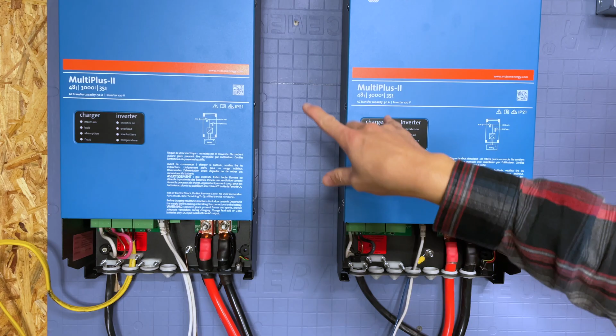So what that really means is it's a 48 volt system. 3000 VA is volt-ampere, so to convert that to real power or watts, depending on the load, take 3000 times 0.7 - that's roughly how many watts it can do for most consumer electronics. If you have more inductive loads, you may want to use a different power factor, but Victron rates these in VA. This is also a 35 amp charger, meaning it can charge your 48 volt battery at 35 amps, granted you're giving it enough juice to do that.